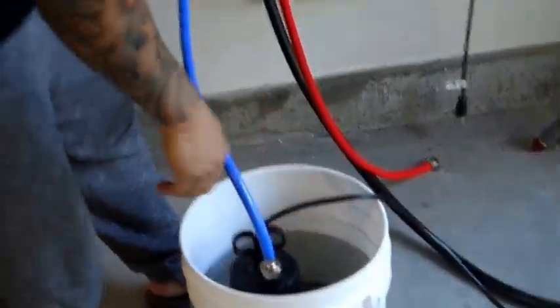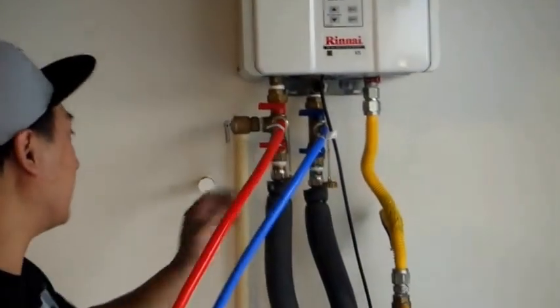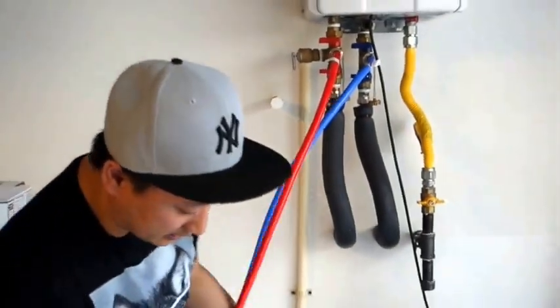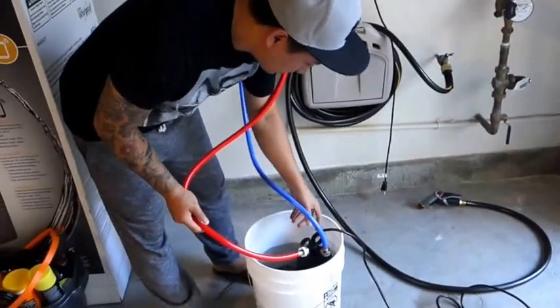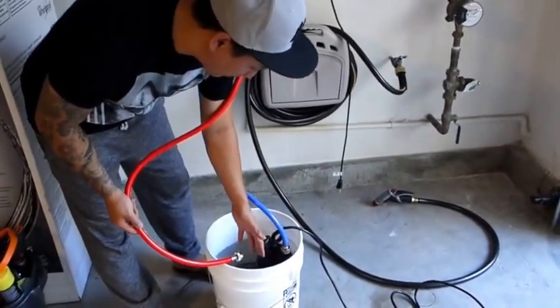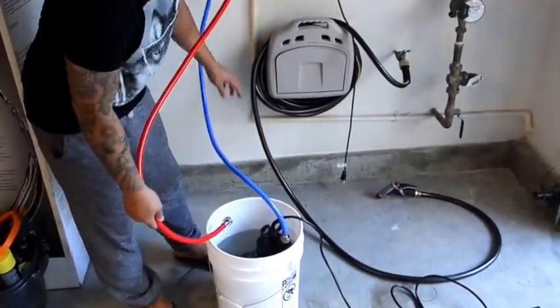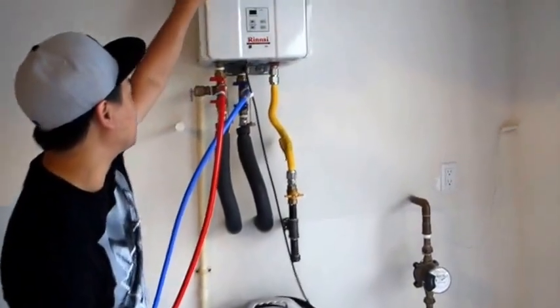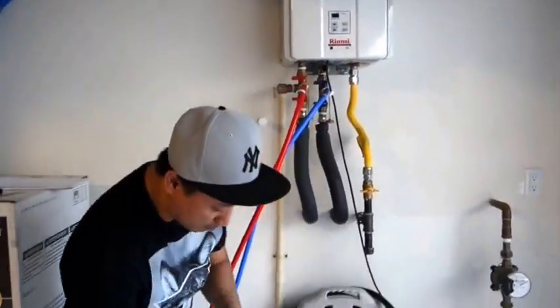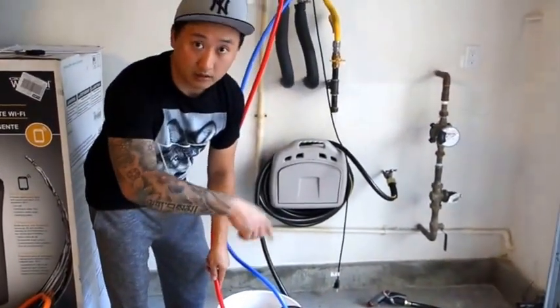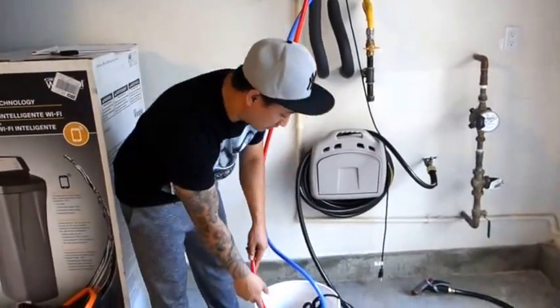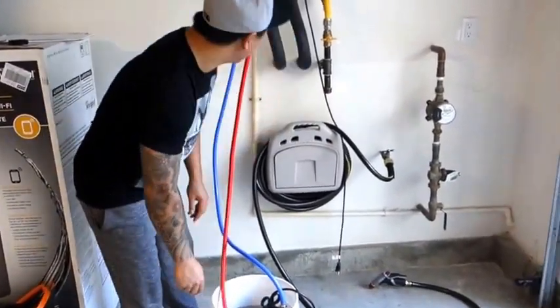So I plug up the hot water outlet as well, and this just sits in the tank. The idea is the pump will suck up the vinegar from the bottom of the bucket, go up the cold inlet, through the system, circulate back out of the hot outlet, back into the bucket, and continue to cycle like that until we're ready.